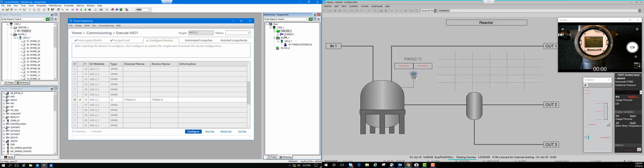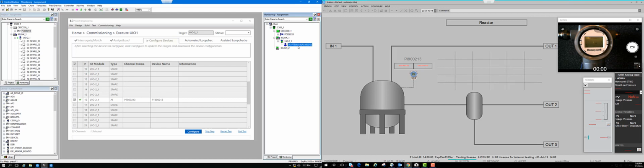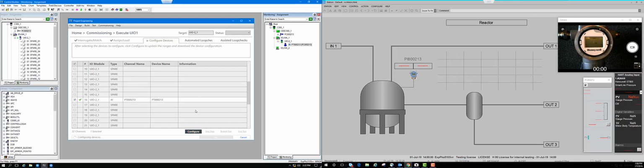Okay, so you see now automatically the instrument has been added to my control execution environment, and also to the UIO2 configuration properties. So what I'm going to do is hit configure. I'm happy with that. I want to go ahead and get that assigned to the channel and to my monitoring project side, and now I'm ready for the loop checks. So let's go ahead and do an automated loop check.